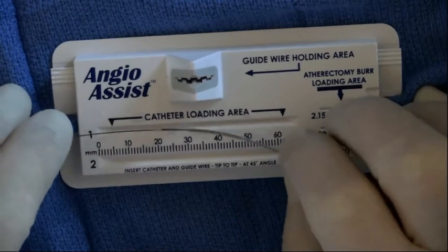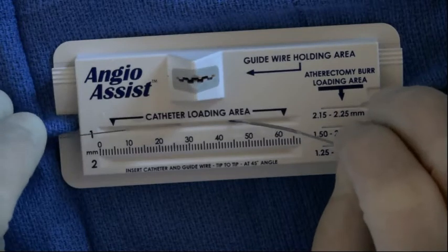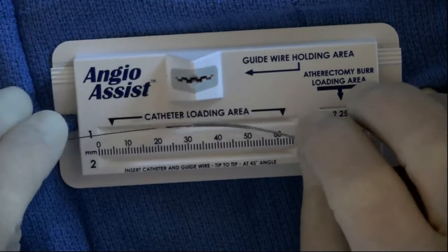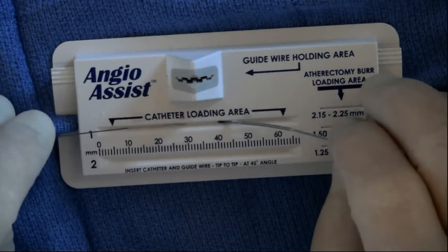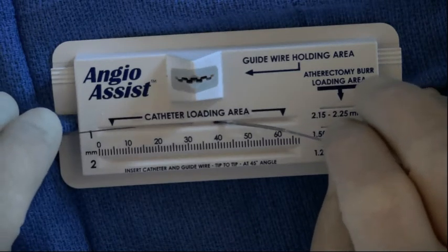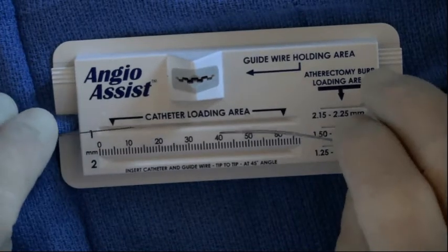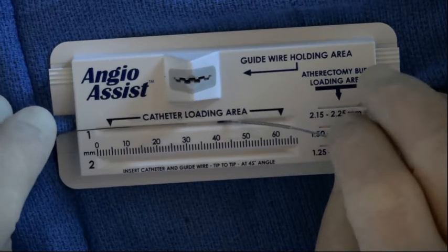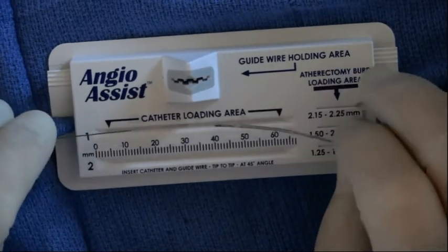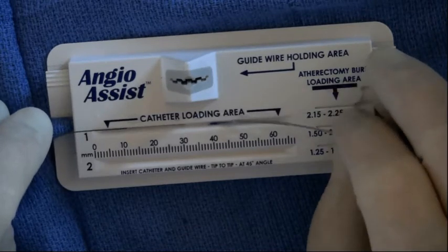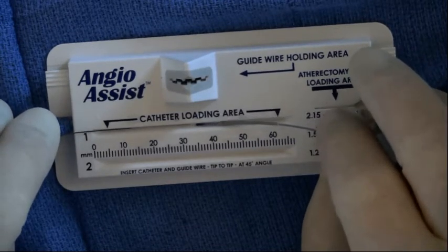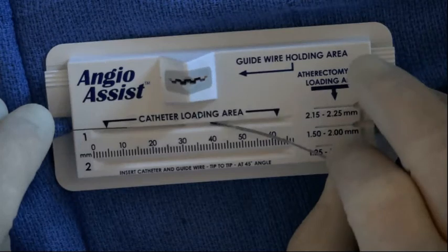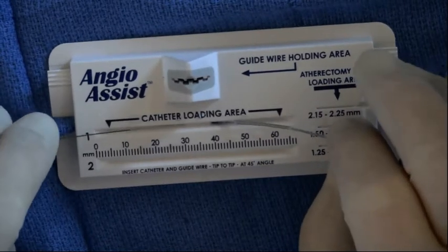catheter lumen. It is important to keep both the wire and catheter straight at a 45-degree angle to the base of the slot. Think of this as bringing 2 halves of a V shape together. You will find the catheter loads very easily and consistently. The only caveats are to keep the catheter parallel to the slot line. Do not angle it from side to side, and do not flatten the catheter or wire within the slot, because this will cause the tip to come off of the bottom and the wire will miss. With very little practice, you will find it loads quite reliably.